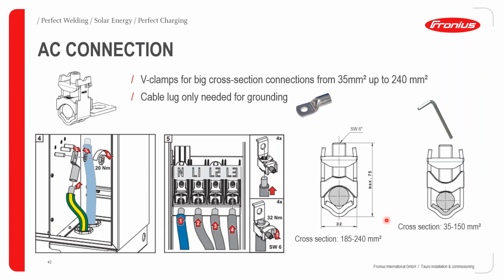With the V-clamps, you can set it up in two positions. If you set it up in the first position, you can take a cross section of 185 to 240 millimeters squared. But if you take this little middle piece over here and swap it over, so if you rotate it completely over, it can then allow you to go for smaller diameters, so 35 to 150 millimeters squared. And you can actually see the hold is quite secure. This really pushes down and puts some pressure on the cable, and again, just makes it a much safer installation. Your cable lug, again, is only needed for grounding.